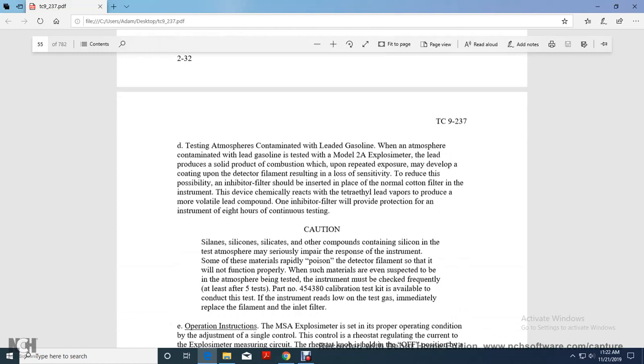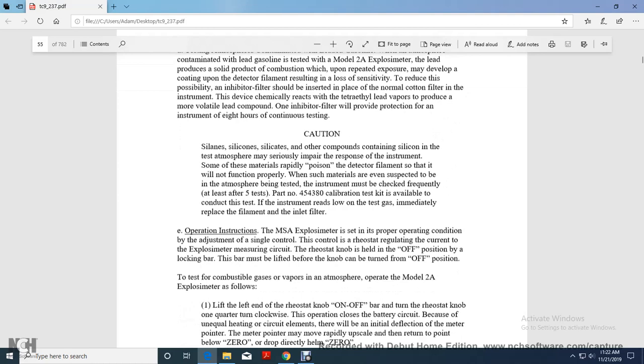Explosimeter lead produces a solid product of combustion. Upon repeated exposure, it may develop a coating on the detector filament, resulting in loss of sensitivity. To reduce the possibility, an inhibitor filter should be inserted in place of the normal cotton filter in the instrument. The filter chemically reacts with the tetraethyl lead vapors to produce a more volatile lead compound. One inhibitor filter will provide protection of the instrument for 8 hours of continuous testing.